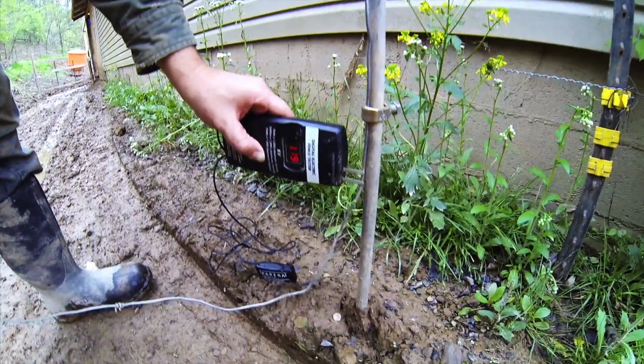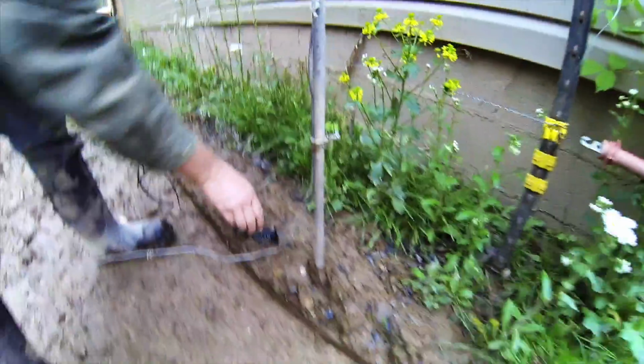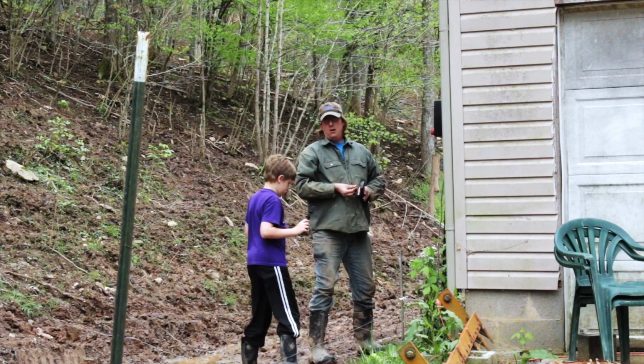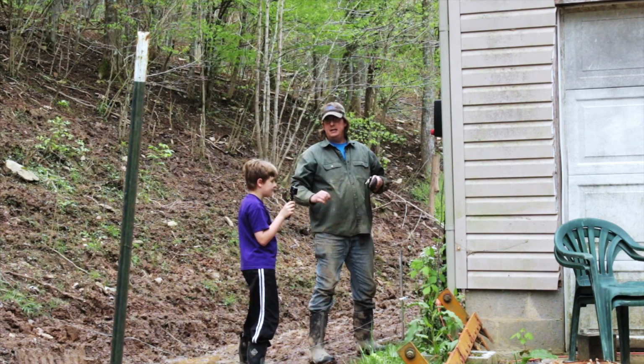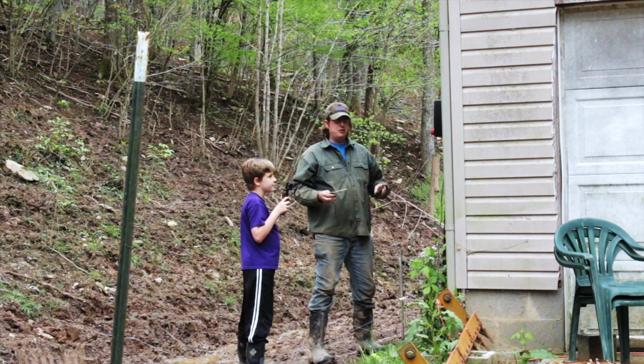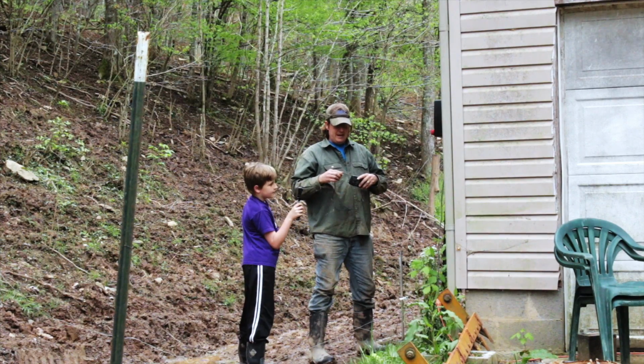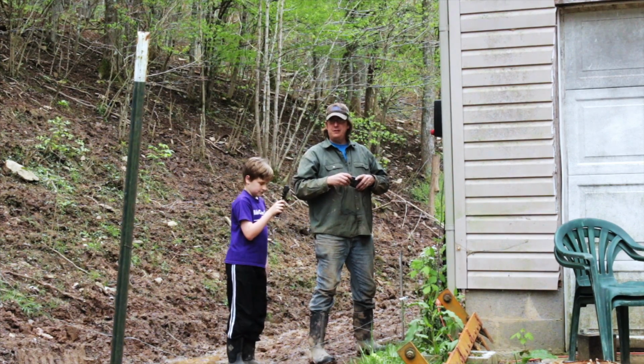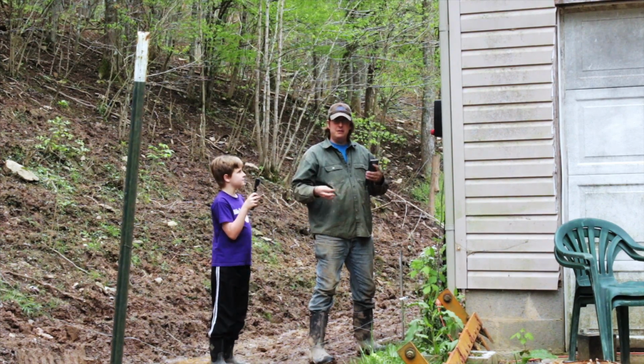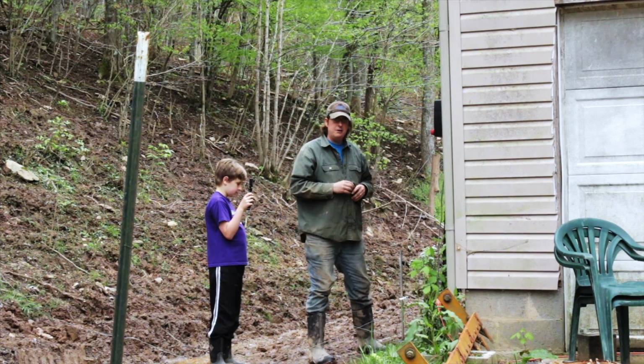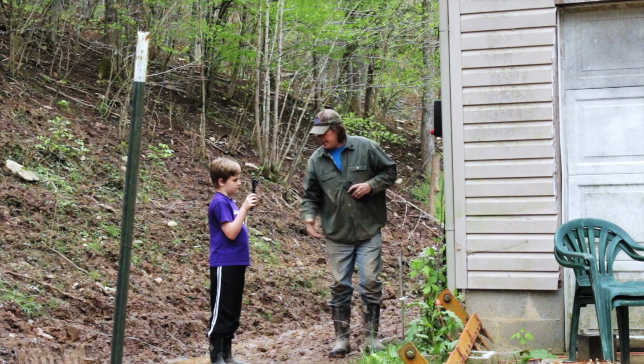Okay, so I'm getting 1.19 kilovolts on my ground. What I've read and understand is that when I get that much voltage on my ground, then I have an issue there. Either my ground field isn't big enough, I don't have enough ground material or rods in the ground, or I've obviously got poor connections.